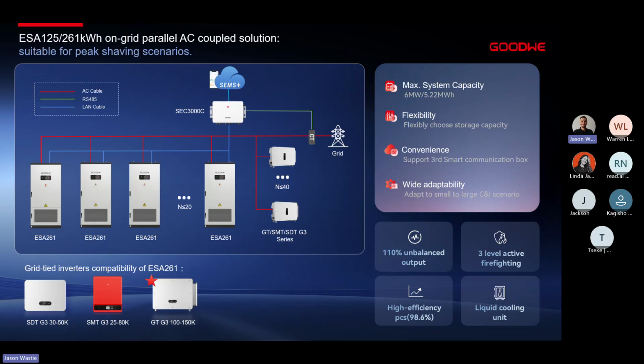So we use these kind of things in on-grid parallel as an AC coupled solution, connect up to 20 of these together. And this is where we look at things like peak shaving or massive system support, just to try and bear some of the load from the AC itself when we can. We connect our grid-tied inverters to the SEC 3000C controller, and through that, we'll be able to use our grid-tied inverters to charge the batteries and allow the batteries to discharge during high peak demand charge times. It's an extremely high efficiency rating on the PCS of 98.6%.